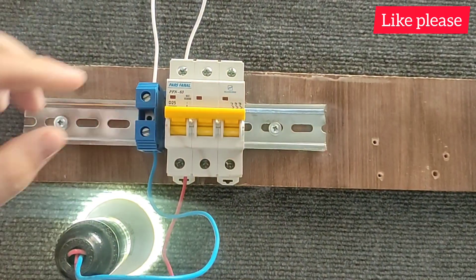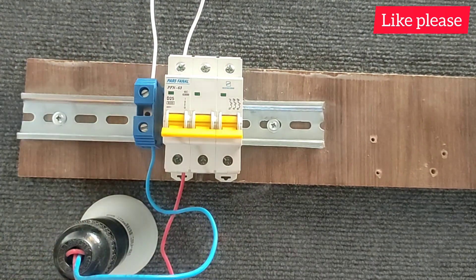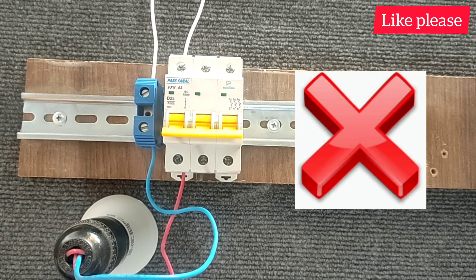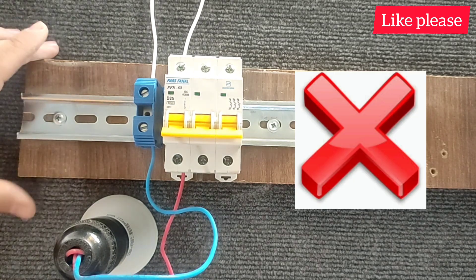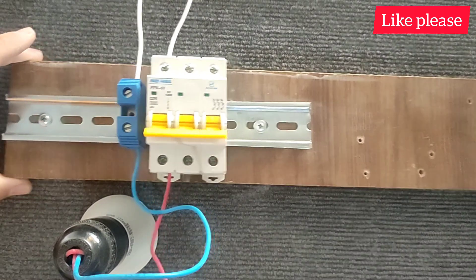You can see that the lamp is activated, but is this method correct? I tell you that this method is never correct because in this case the current only passed through one of the blades of the switch. And in this case, if a short circuit occurs, the switch cannot work properly and cut off the circuit.